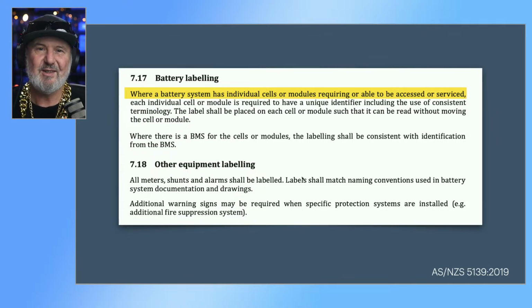Now, unlikely to be cell level, because that would be a very granular kind of DIY system, but these days generally cells are packaged into modules, something useful like a 48-volt module or similar, and those are either rack-mounted, stackable, or ground-mounted. And on each cell or module such that it can be read without moving the cell or module. So, yeah, labelling that's not visible without disassembly is not appropriate. Where there is a battery management system, a BMS, for the cells or modules, the labelling shall be consistent with the identification from the BMS. So this really relates to things like shutdown procedures.